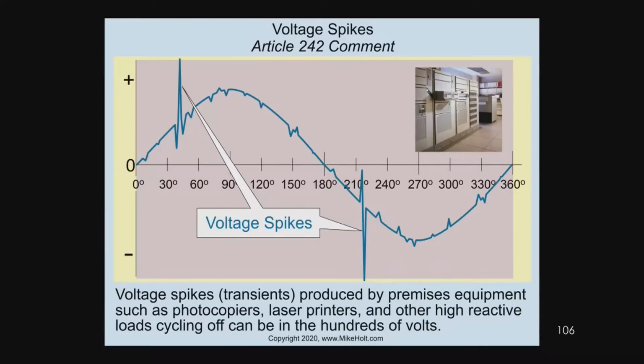The utility is outside, and they're trying to deal with these lightning events, which cause this very fast, very high amount of energy, high voltage. No matter what they do, a part of that energy is going to be transferred from the primary of their system over to the secondary winding. Yes, it affects the entire system. Because the primary voltage is transformed into the secondary voltage, Jacob, if there are momentarily millions of volts, or hundreds of thousands of volts, striking the primary, well, that's still part of the primary winding, and it's going to spike something on the secondary. Okay? All right, so now let me read this. Eric, did you want to say anything at all on that?